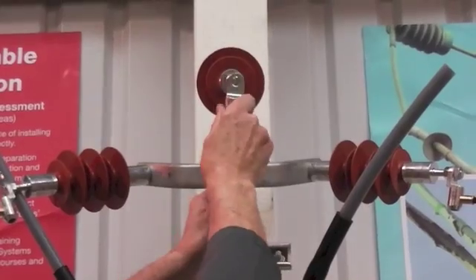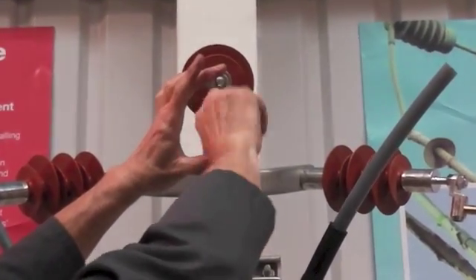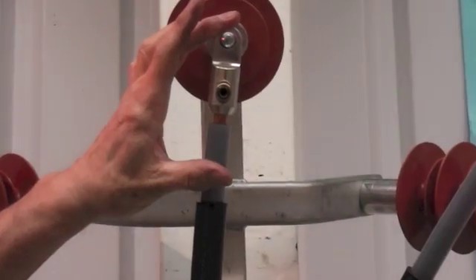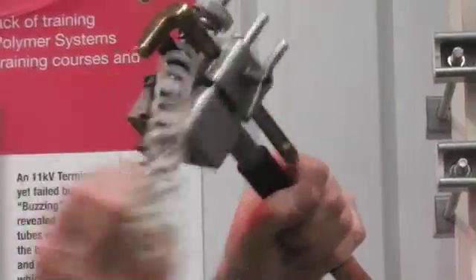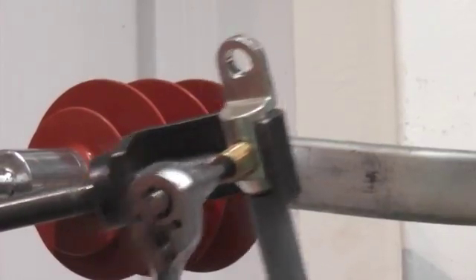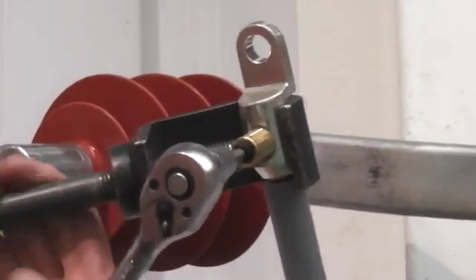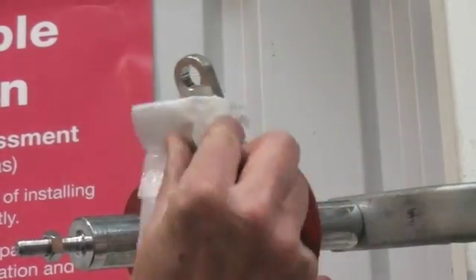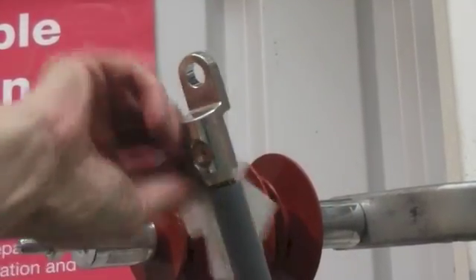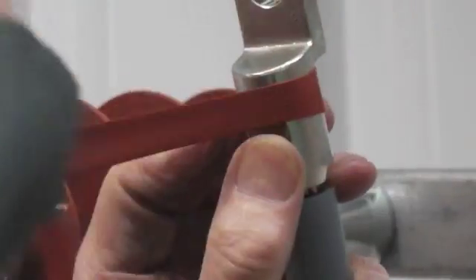We're now fitting mechanical connectors. These are already water-blocked and are suitable for copper or aluminium conductors. You'll need a holding tool to use these to support the cores. Clean and grease. If there are any large voids, you can fill the hole with the mastic tape supplied. And then wrap the red mastic sealing tape around the lug barrel and down onto the core.